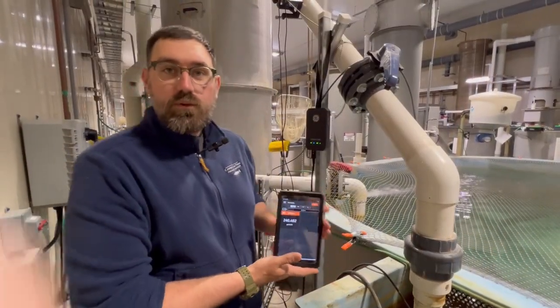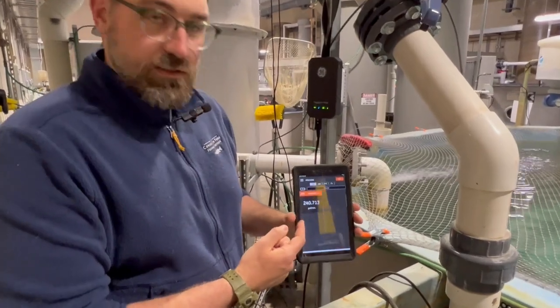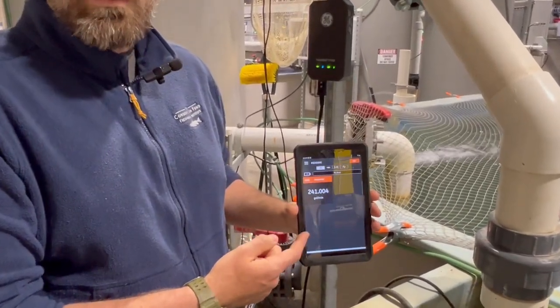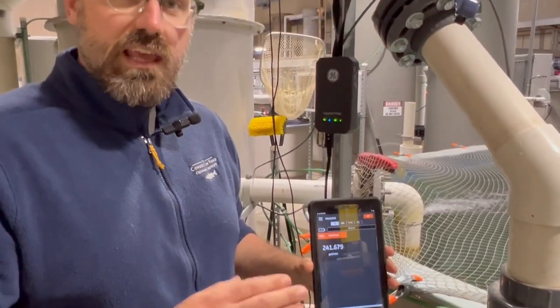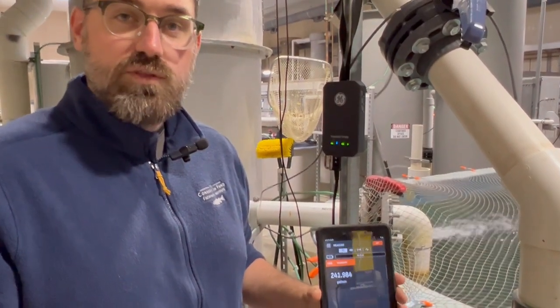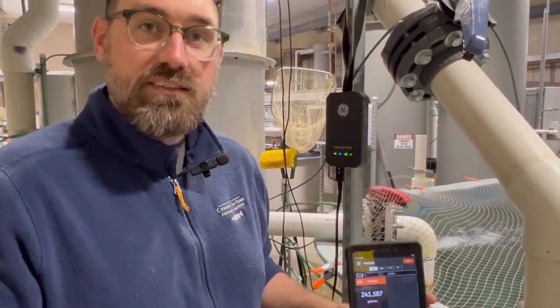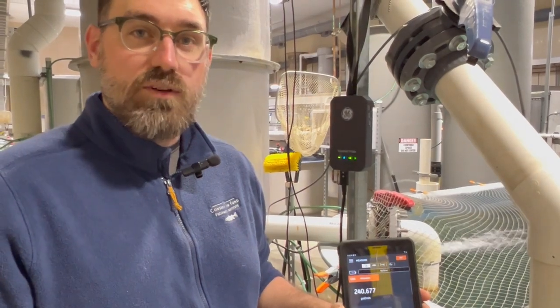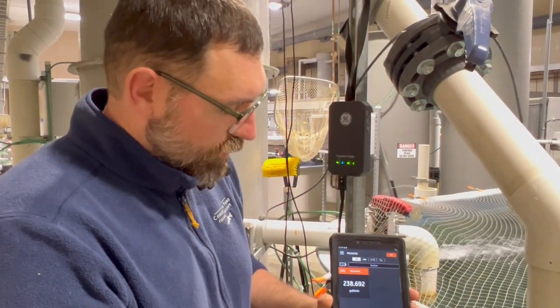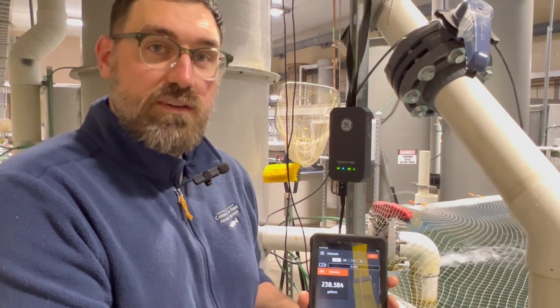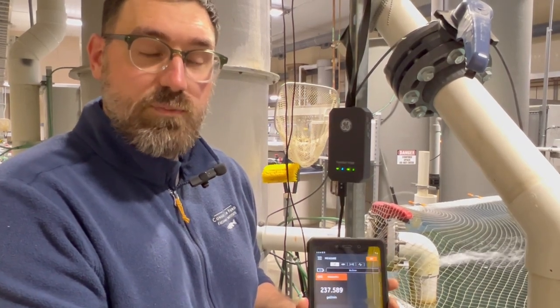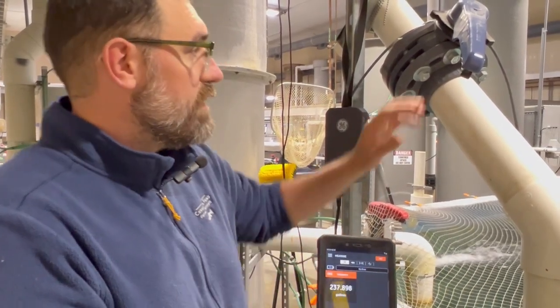Okay, we found the problem. We're pumping 240 gallons a minute to the LHO when the LHO is engineered to only handle 230 gallons a minute. So that excess water can't flow through the LHO and it's overflowing. So we're going to go ahead and make an adjustment in real time to get that flow back in spec and get that LHO functioning properly.